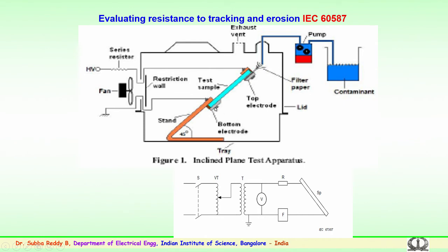The test sample is here, this is the bottom electrode, this is the top electrode, and the top electrode is connected to a peristaltic pump, where the water droplets at regular intervals go onto the surface of this insulator sample, and the high voltage is applied between the top electrode and the bottom. The voltage, again it is known, either 3.5 kV or 4.5 kV as per the standard information. So this is how the arrangement is to be made for studying the inclined plane experimentation for both AC and DC application. The standard very clearly specifies for AC application.